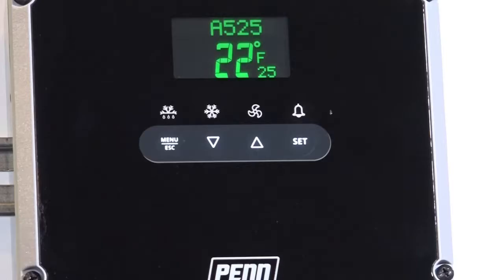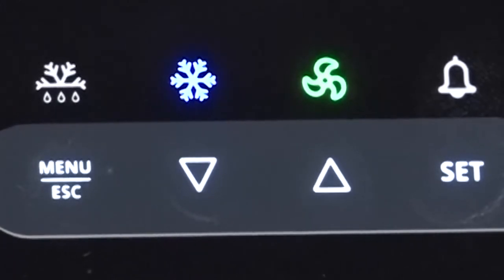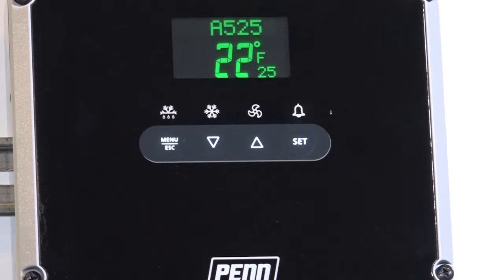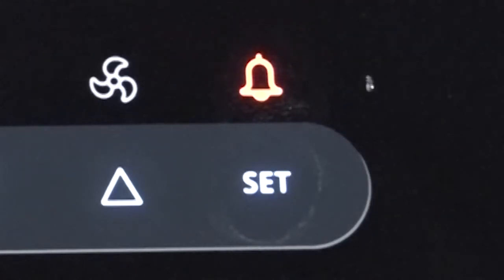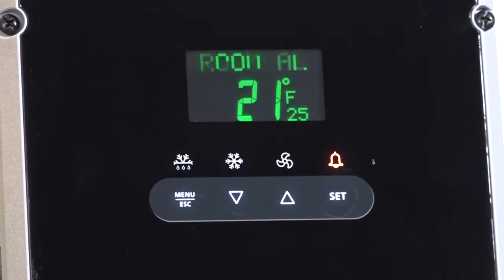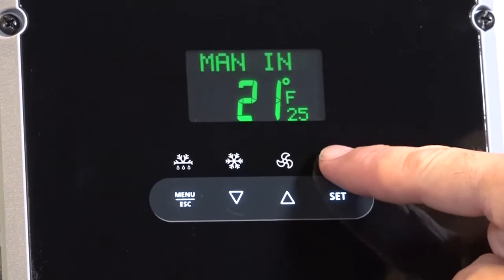The fan icon will be illuminated when the evaporator fan is on. This will usually be any time the snowflake icon is illuminated, but there may be times that the fan is running without a call for cooling, such as during a drip defrost cycle or if the low-speed fan operation is initiated. The last icon is the alarm icon. The alarm icon will only illuminate when an alarm condition occurs. If an alarm sounds, press the alarm icon to silence the alarm.